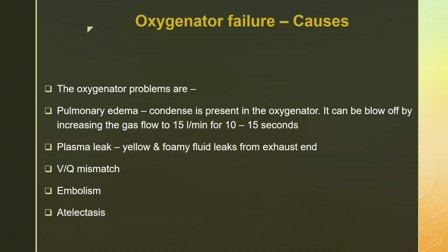If the membrane edema persists, you will see an increase in CO2, because the sweep gas you've set is not actually going through fully; it's going less. So your CO2 will start going up, and that's why you have to do this blow-out every 4 hours by default. You have to instruct your staff to do it every 4 hourly.